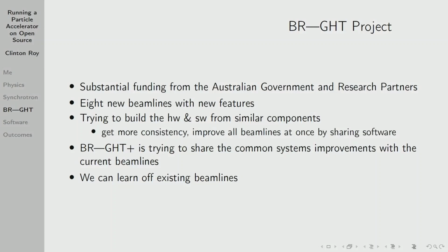What we're trying to do with the new beamlines is design them all in the same way as much as possible, so 80, 90% the same. We have the same physical layouts, the same electricity set up, the same control systems, the same safety systems, such that we can share expertise and knowledge and standardise things. When a motor dies over here, we've got a spare here because we're all using the same sort of motors, unlike what it is now.